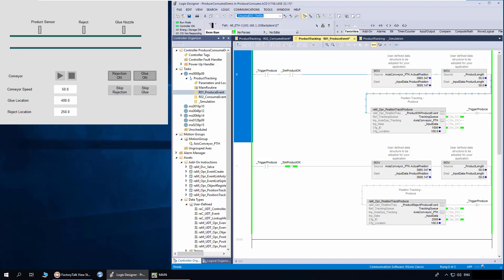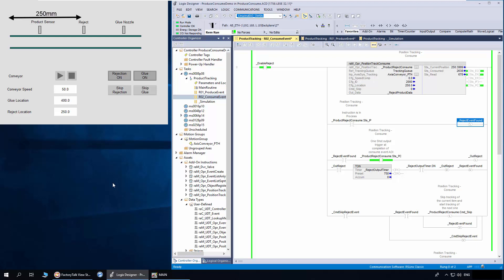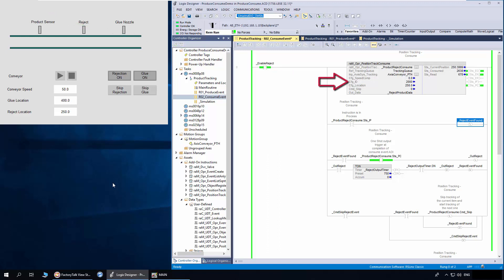I'll open the consume routine. Here we have two consume logics: one for reject and another for glue. The reject mechanism is considered to be set at 250mm on the conveyor and configured to track events with ID 2000. The status PC bit and timer logic are used to trigger the output.